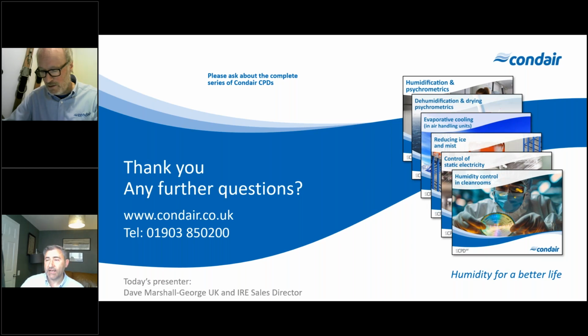Water quality can have a dramatic effect on the humidifier, and also depending on the type of humidifier. So if we're using electric steam generation, let's say with an electrode boiler, we're looking for water quality between 125 and let's say 600 microsiemens. It is important that in a hard water area, softened water is not an ideal option. If we soften water, we're just replacing the calcium with sodium, and that can have effects on the capabilities and the boiling cycles and drain cycles of the humidifier.